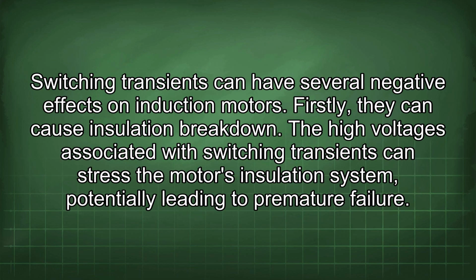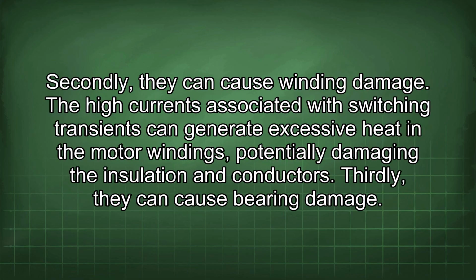Switching transients can have several negative effects on induction motors. Firstly, they can cause insulation breakdown. The high voltages associated with switching transients can stress the motor's insulation system, potentially leading to premature failure. Secondly, they can cause winding damage. The high currents associated with switching transients can generate excessive heat in the motor windings, potentially damaging the insulation and conductors. Thirdly, they can cause bearing damage.